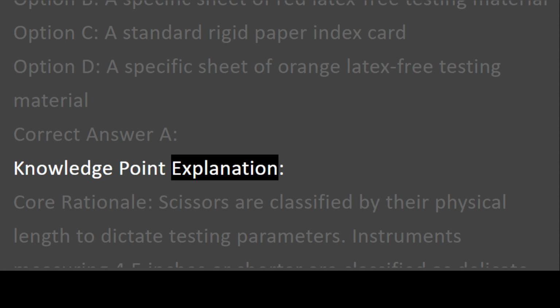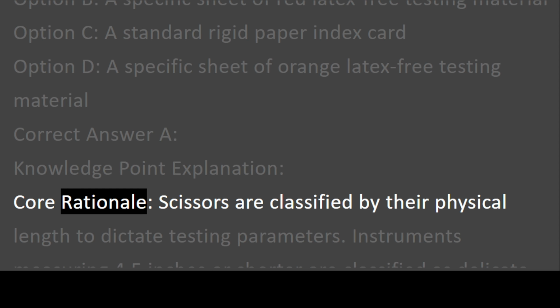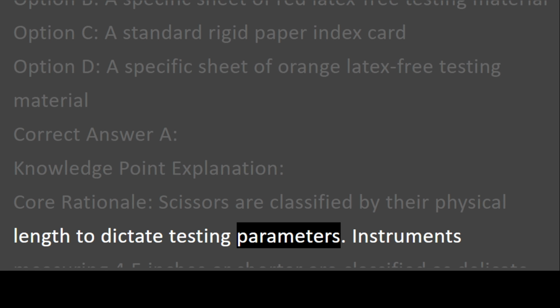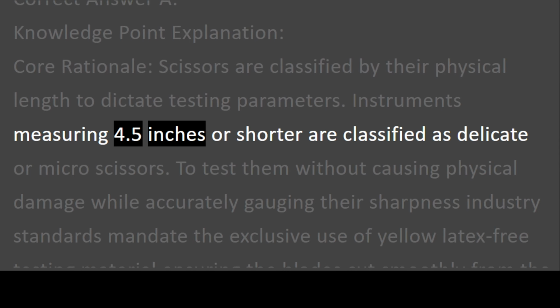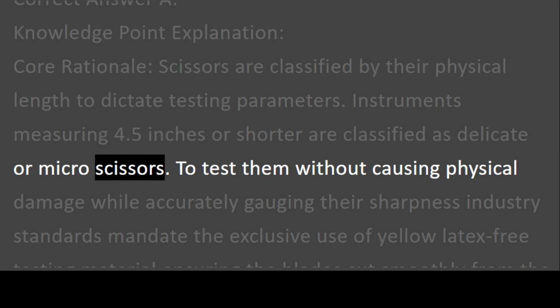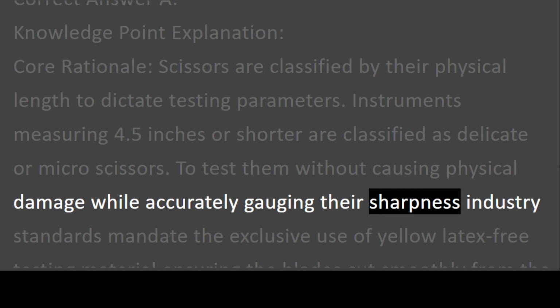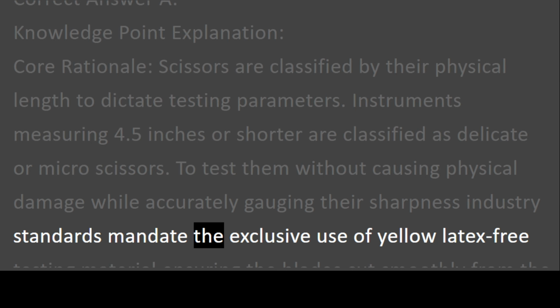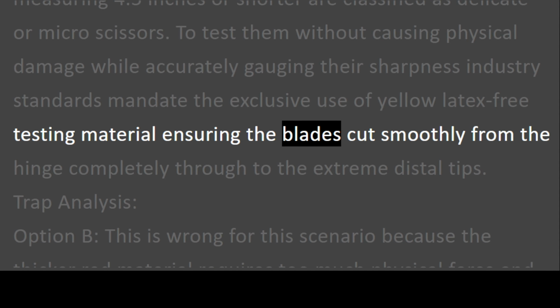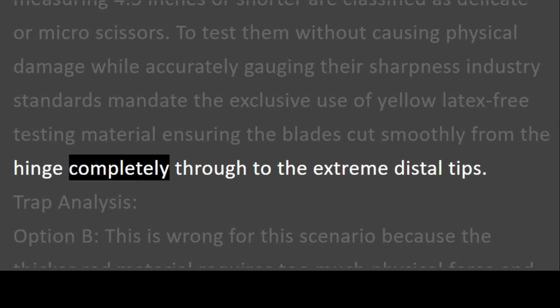Knowledge point explanation. Core rationale. Scissors are classified by their physical length to dictate testing parameters. Instruments measuring 4.5 inches or shorter are classified as delicate or micro scissors. To test them without causing physical damage while accurately gauging their sharpness, industry standards mandate the exclusive use of yellow latex-free testing material, ensuring the blades cut smoothly from the hinge completely through to the extreme distal tips.